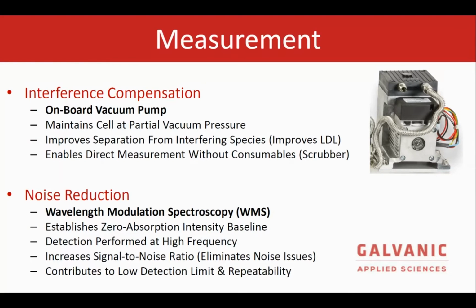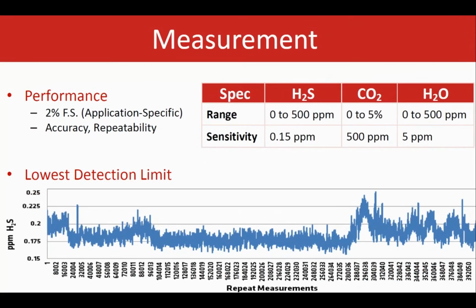In order to get a better sensitivity for the analysis, we also use a fairly common feature, which is called the WMS, or the wavelength modulation spectroscopy. Using this technique, without going too far into details on how that works, the whole goal is to make sure we increase the signal to the noise ratio using this technique for the data processing. And in combination with the vacuum pump as well as the Herriott cell design that we are using for the analyzer, we can finally provide a very low detection limit measurement with great accuracy, great isolation for the lines of our interest.